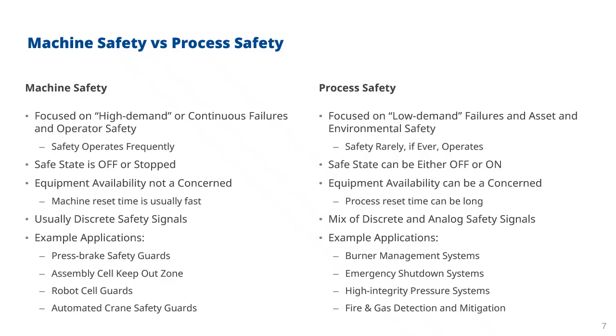So you can think of it a bit like an insurance policy, but you need that safety just in case. Now, with process safety, the safe state is usually off. So, for example, with emergency shutdown, you normally want to close a valve and stop operation of the plant, but it can also be on. If you've got a fire and gas system, you might want to open the valve to deluge the plant with halon or whatever the extinguishing material is. So, safe state can be off or on.